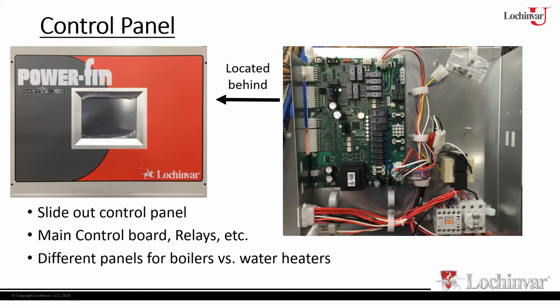All right. So you look at the original power fins, what you had in that control panel, right? You had a transformer, you had a pre-purge relay, a post-purge relay, a fan relay, an ignition module. You had separate thermostats. You had all these individual components that you had to keep up with. Here, you've got it all in one board. So you have a much thinner, if you will, much leaner control panel. So you just got one component that you're dealing with.